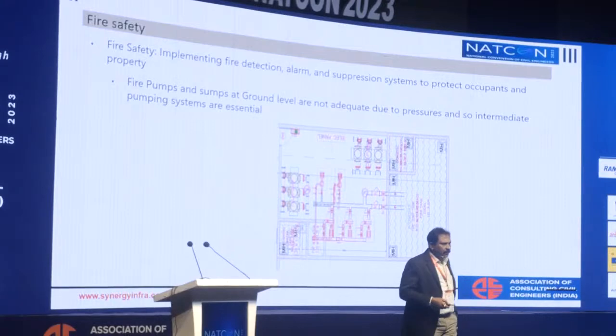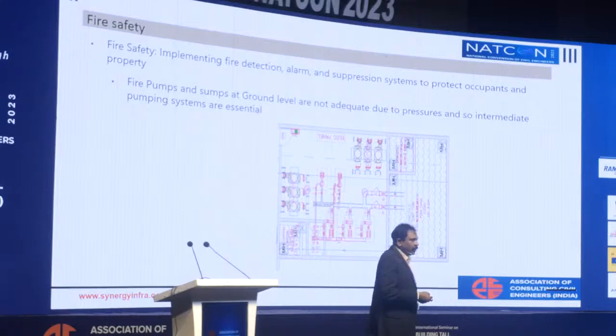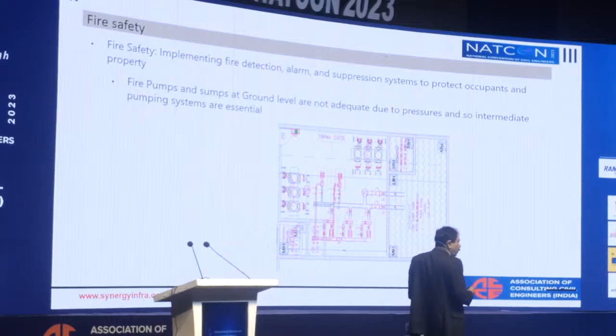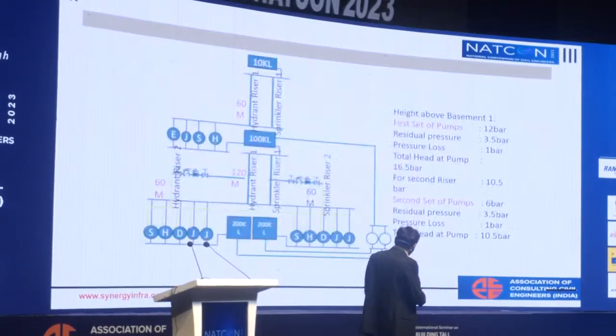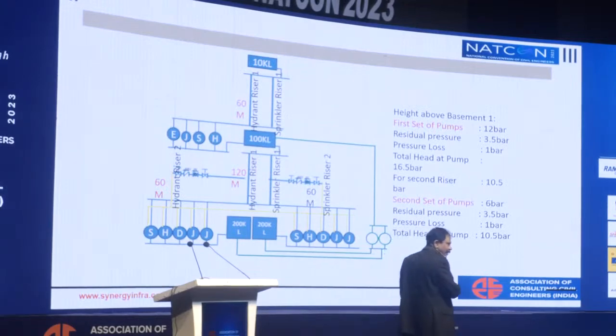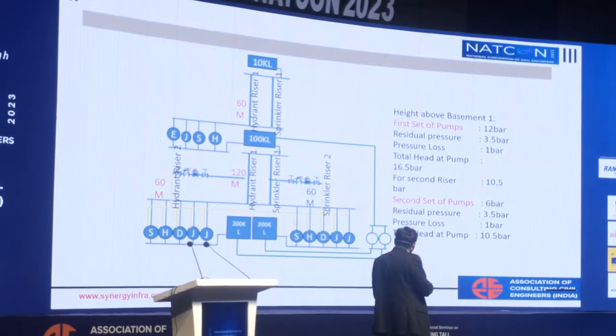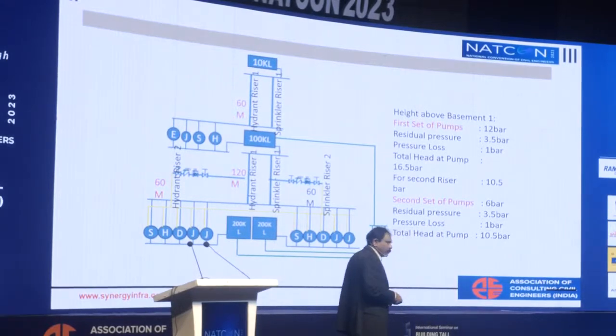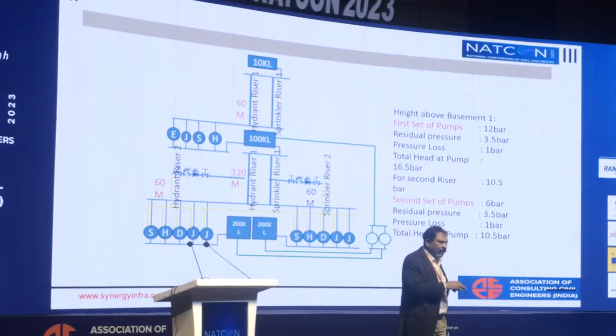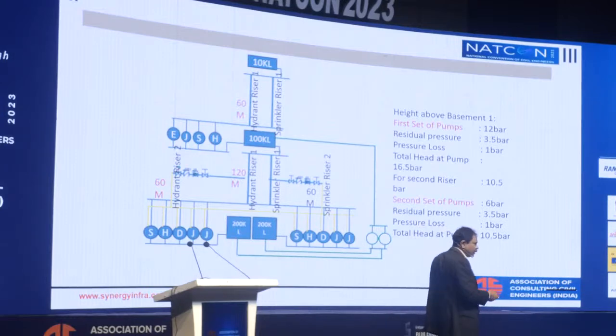But since they are now insisting on 150 meters, we need to have space for these things, and we also have to see that the occupants of the buildings are not disturbed whenever testing is going on for these fire pumps. So we have to make sure that they are structurally isolated from the regular slabs, as well as take care of the load of the water at that particular level. We also have an issue of overflow of water from the tanks not causing inconvenience to the other occupants. This is for a 180-meter building. So we suggested to the fire department, why at 150 meters we can take it at a lower level, so that we can optimize even the pump capacities, which is now accepted by them.